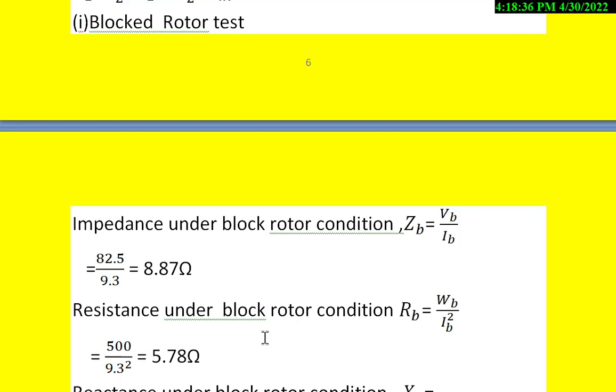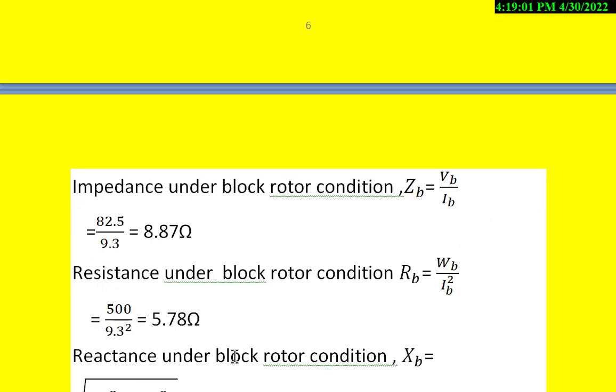Resistance under blocked rotor condition: RB = WB/IB². WB is 500W and IB is 9.3A. After simplification, RB = 500/9.3² = 5.78Ω.